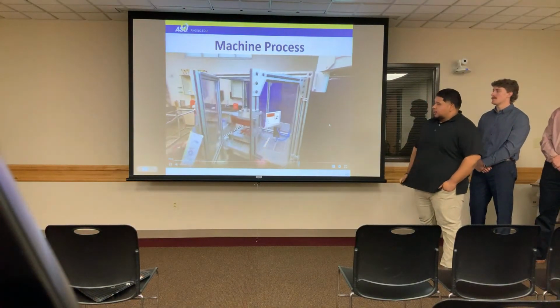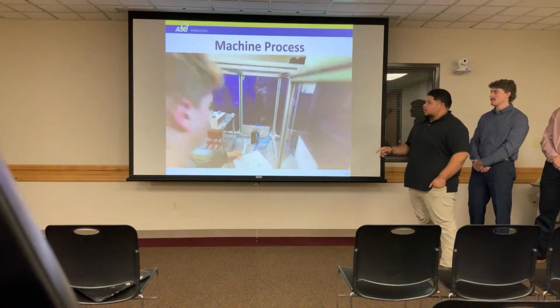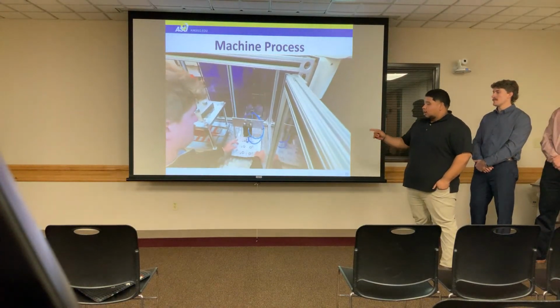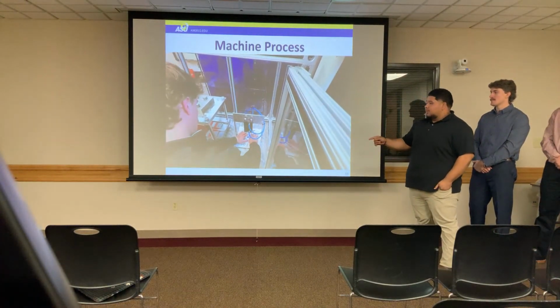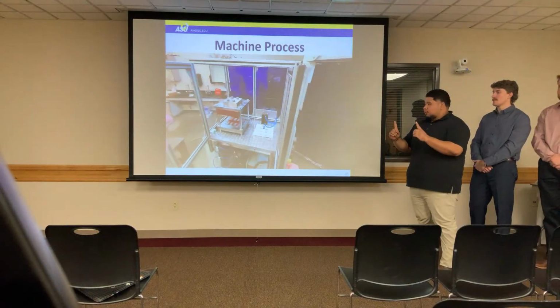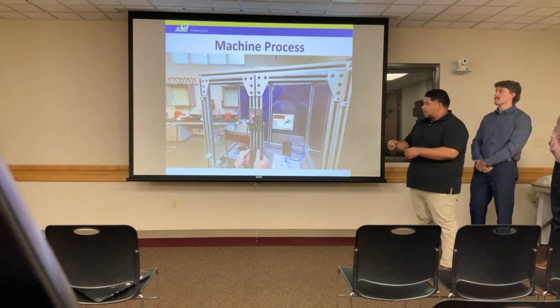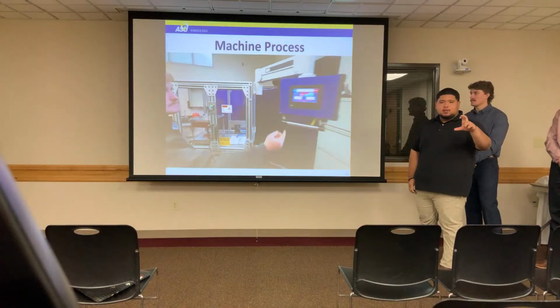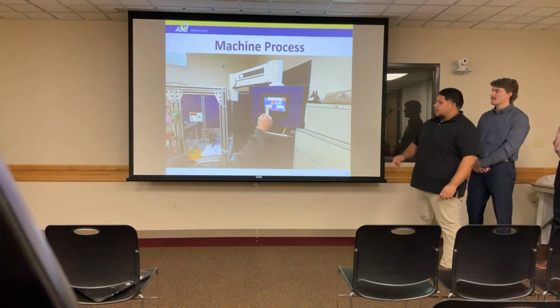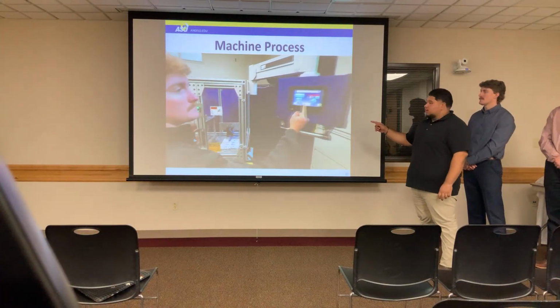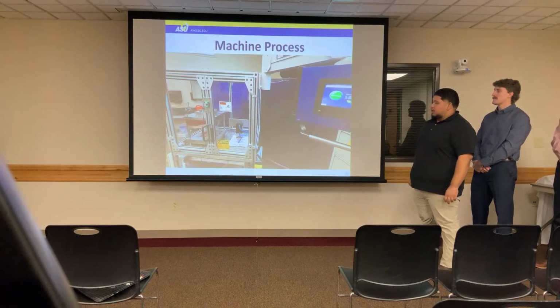So here you see Wes opening the doors, which breaks those interlock switches. You see it turning red. On our evacuation station, as well as our press assembly, we actually have two little rods sticking out that allow you to align the package on there. If y'all have the package, y'all see two little holes on them. He goes over the HMI, resets the door lock, which is very important, and then starts our evacuation process.